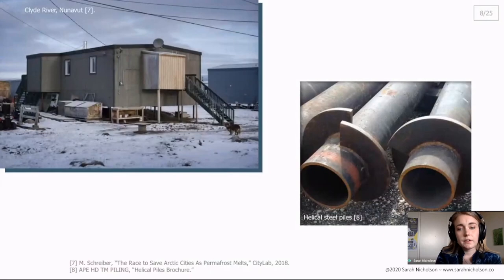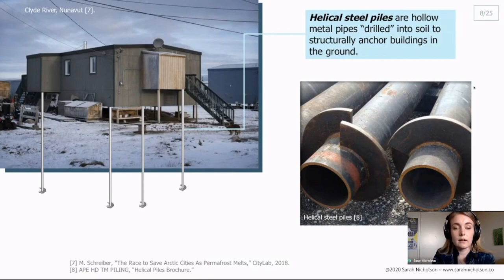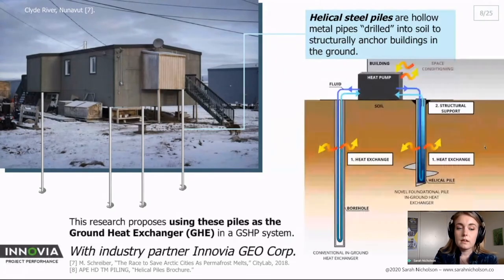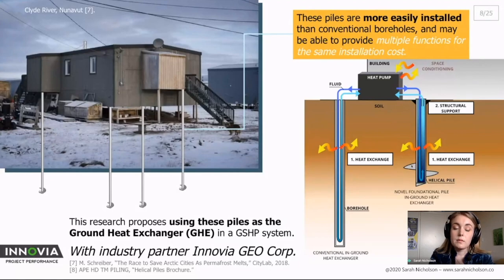So investigating this further, with helical steel piles which are existing in-ground equipment used in some northern communities to structurally anchor a building in the ground. These are essentially hollow steel piles which can be screwed in. With Innovia GEO Corp, our industry partner, we're looking at using those piles to replace the conventional in-ground heat exchangers. So here is a conventional borehole which is hundreds of feet deep and here is this novel pile heat exchanger which is much shallower and easier to install. As well it's possible that this pile could provide two functions at once, being both the structural anchor and the heat exchanger. So this would reduce the original cost.